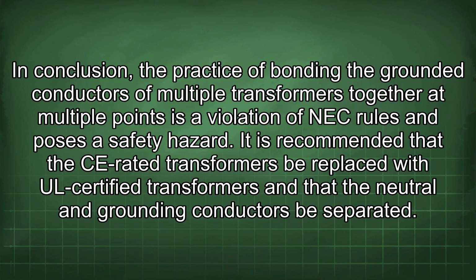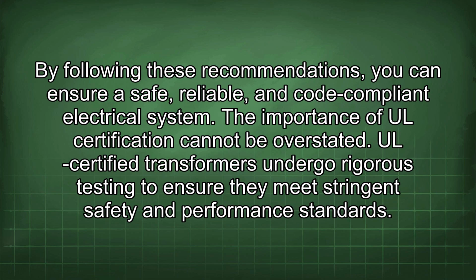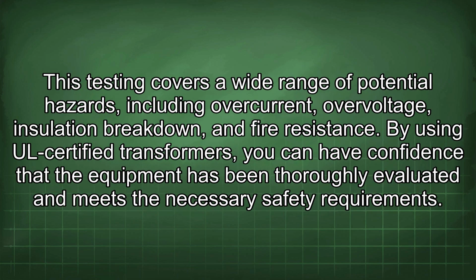It is recommended that the CE-rated transformers be replaced with UL-certified transformers and that the neutral and grounding conductors be separated. By following these recommendations, you can ensure a safe, reliable, and code-compliant electrical system. The importance of UL certification cannot be overstated. UL-certified transformers undergo rigorous testing to ensure they meet stringent safety and performance standards. This testing covers a wide range of potential hazards, including overcurrent, overvoltage, insulation breakdown, and fire resistance.